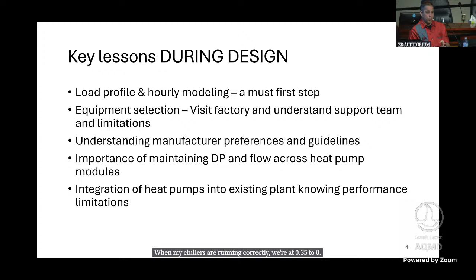If we can produce enough chilled water, then the campus chillers, the 1,000-ton chillers I use, don't have to run. Instead of running a 1,000-ton chiller at 150 tons or 50 tons, which isn't very efficient - when my chillers are running correctly, we're at 0.35 to 0.5 kW per ton, but when they're running at 35 tons, they're like 1.75 kW per ton. So now we're able to just shut them off, use them to circulate water through the campus, and take advantage of all the free tonnage we're producing on the heat pumps. There's a huge byproduct benefit there.